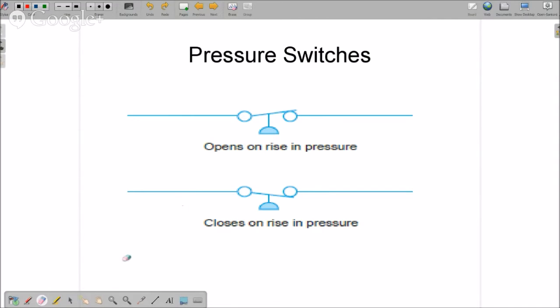In most residential HVAC equipment, the pressure switches are safety devices. They are normally closed, and if the pressure in the system gets too high, it's going to pop that switch open and stop everything to protect the compressor. Same thing if the pressure gets too low - it's going to pop it open and stop the equipment to protect the compressor.